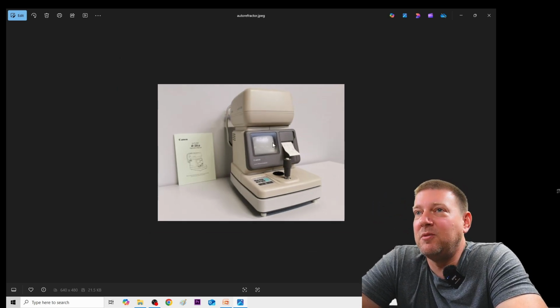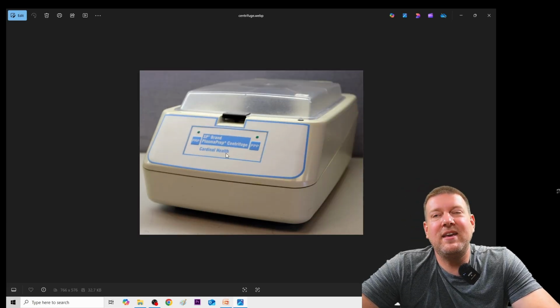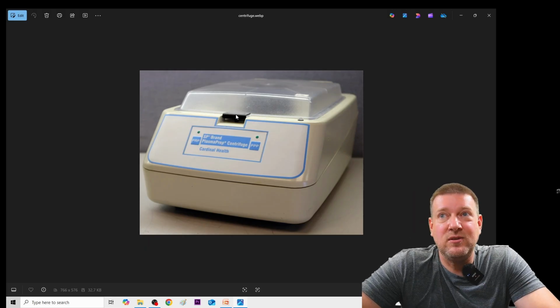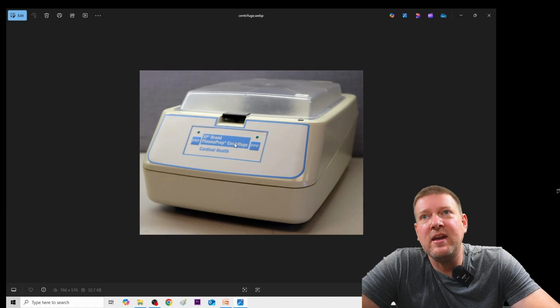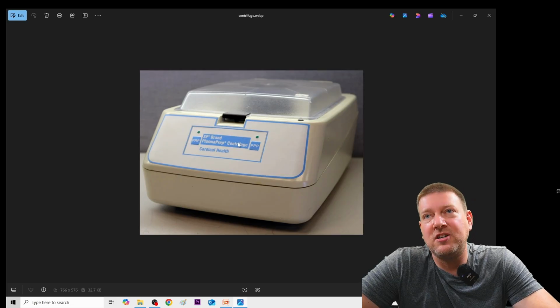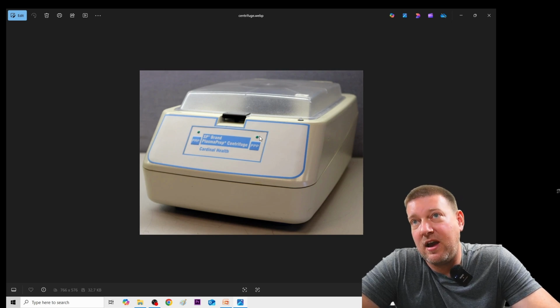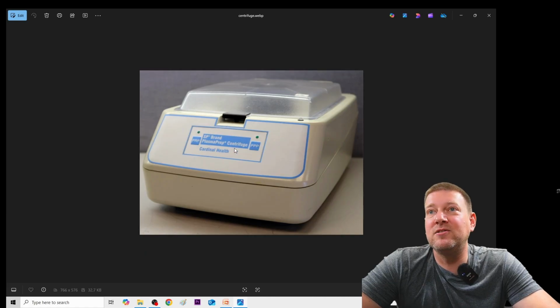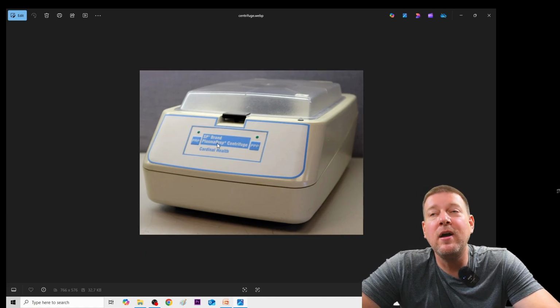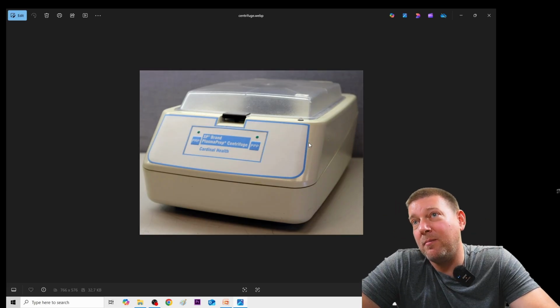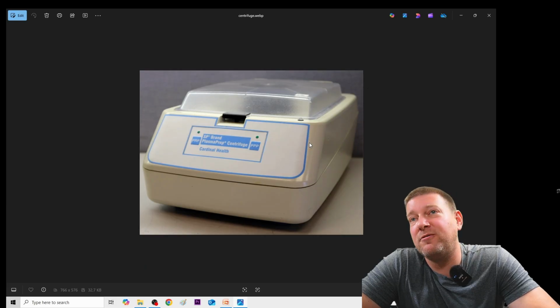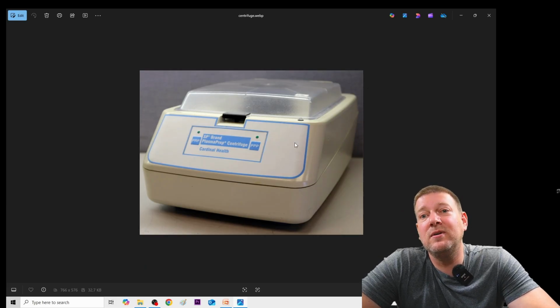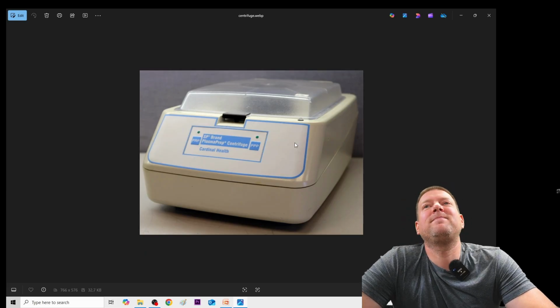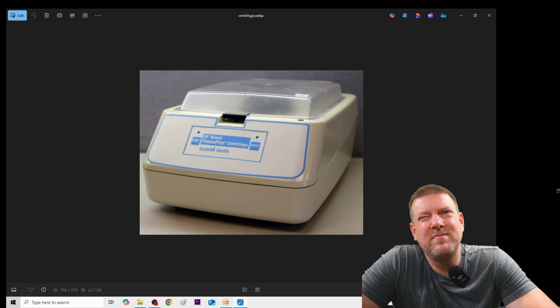Again, you're going to see a lot of similarities in these products, and there is going to be some overlap. So this guy here is a centrifuge. I showed you a Gen 1 centrifuge. Now this one here, all day long, is a Gen 2 centrifuge. This one does have AC power in, but you can see it has a very simple logic controller. This guy here is probably based on a 555 type timer, because all you're doing is selecting this timing or that timing, that's all you're doing on this guy. So two buttons, and there's going to be a little rectifier in there to rectify the AC power. Now, the motor could be run by AC power on this guy. Again, I don't know, but judging from the image and from what I've seen, this guy here looks like a Gen 2. Now, if the motor runs off PWM and stuff like that, then it would be a Gen 3. But to me, this guy here is probably a Gen 2.